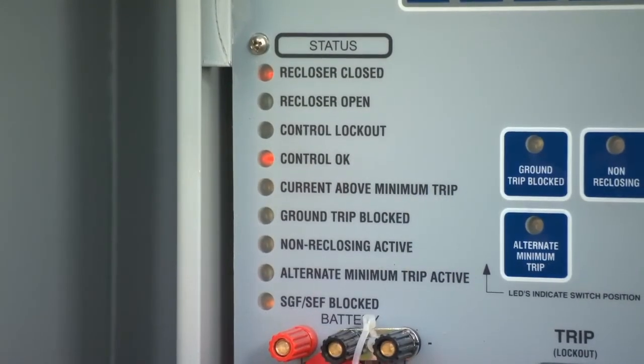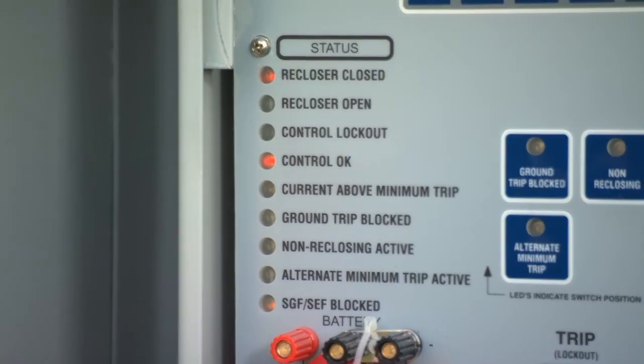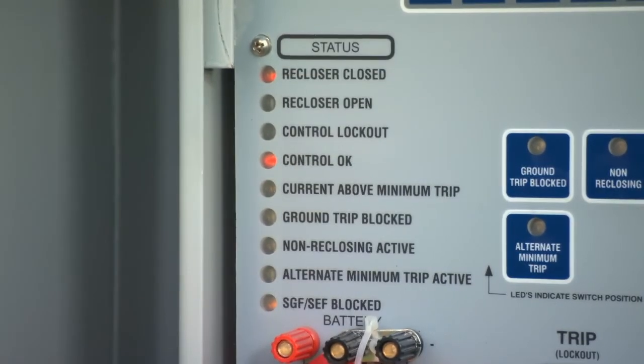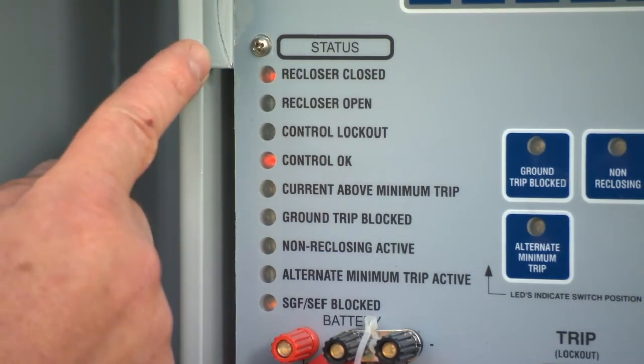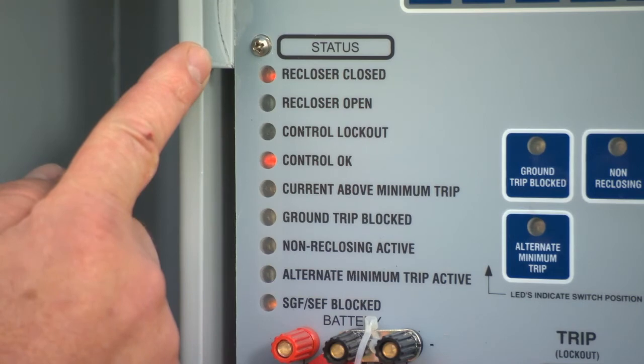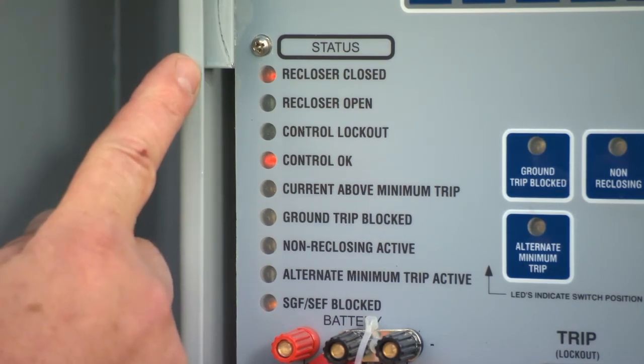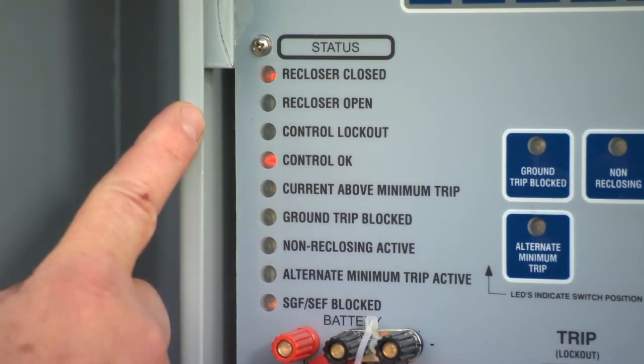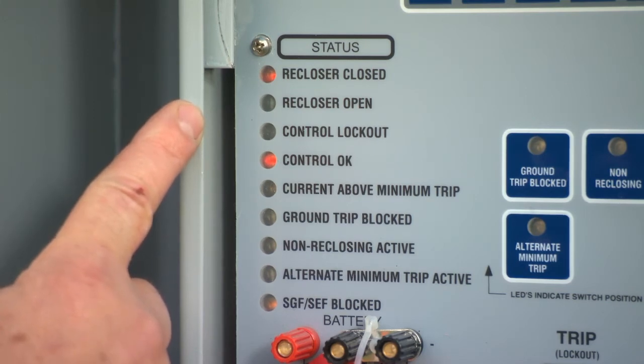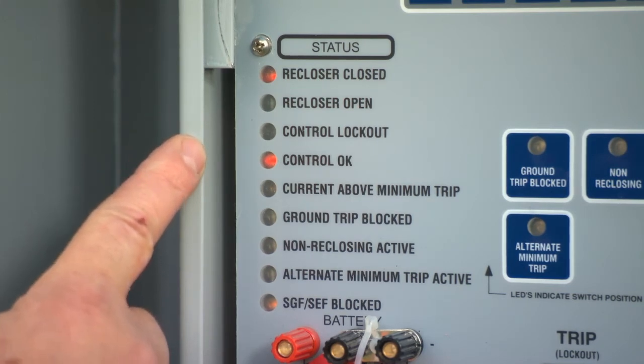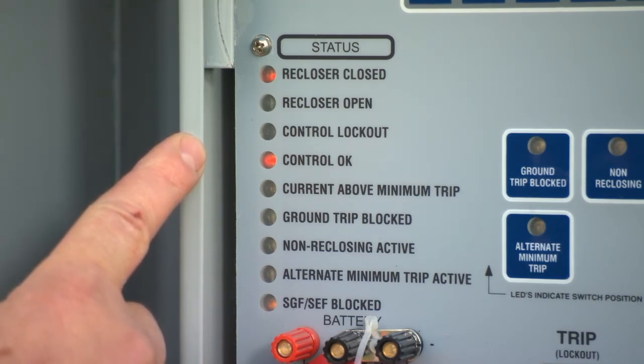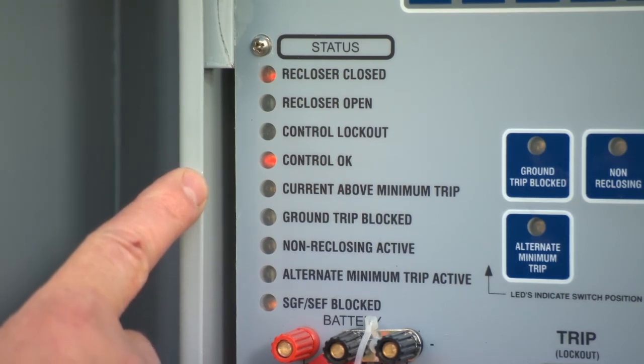Down the left side of the control panel, below the fault targets, you will see indications as to the recloser's status. Starting from the top is recloser closed, which is now red, indicating that it is now closed. Next is recloser open, which will light up green if the recloser is open. Control lockout will illuminate red if the control has been tripped open manually or gone to a lockout state. Below that is Control OK, which is a self-check that tells you that the control is OK.